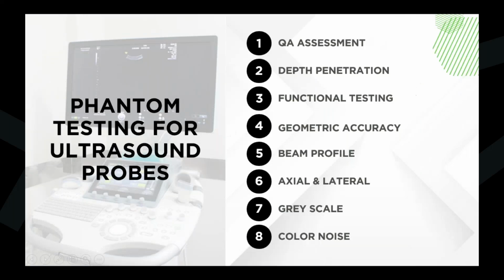All right, phantom testing for ultrasound probes, or quality assurance tests for ultrasound transducers. Is everybody familiar with a phantom? Basically, it's just a tissue mimicking device that you use for quality assurance testing on your ultrasound transducers. These are the tests that we're going to cover today. The first one is what we call an air scan. So it's just an air scan of the probe.